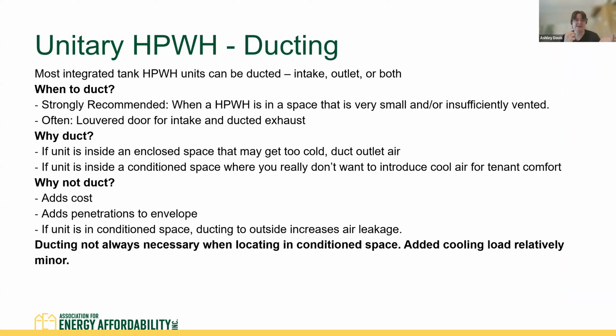So when it comes to ventilating unitary heat pump water heating, a pretty common strategy is ducting. Most of the integrated tank type heat pump water heaters out there have a way to be ducted. Some manufacturers even provide kits so that you can very easily hook up ductwork to either the intake or the exhaust or both. Strongly recommended to duct when your heat pump water heater is in a space that's very small or insufficiently vented, because it's just more deliberate about really removing the cold air. A lot of times we will see a louvered door for intake and then ducted exhaust to the outside. So, if you're in an enclosed space that might get too cold, it's a good idea to duct your exhaust, because then you don't really have to worry about having other sufficient ventilation, right? You've already sent the cold air outside your closet.